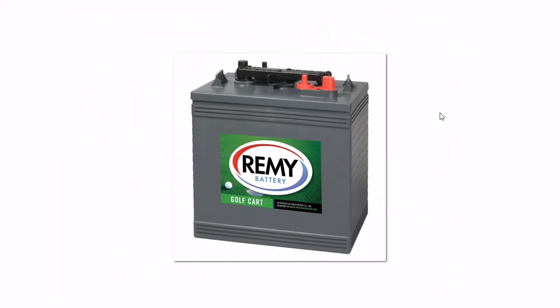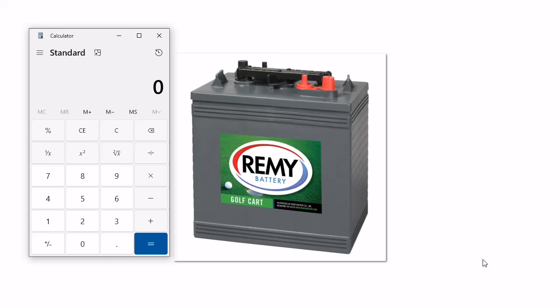Here is a typical high amperage battery. This particular battery is 220 ampere hours at 6 volts. Let's argue that the battery has been discharged 50% and we would need to charge it back up at 110 ampere hours. If we charge this at 5 ampere hours, it's going to take 22 hours to charge this particular battery. If we charge it at 20 amps or 20 ampere hour rate, we've cut it down to 5.5 hours. So that's why it is highly desirable to charge this at a higher current, but not so high as to damage the battery itself.